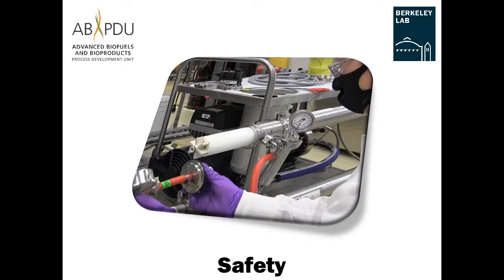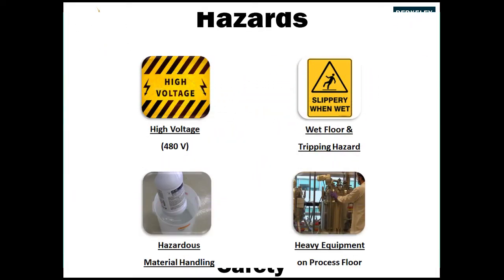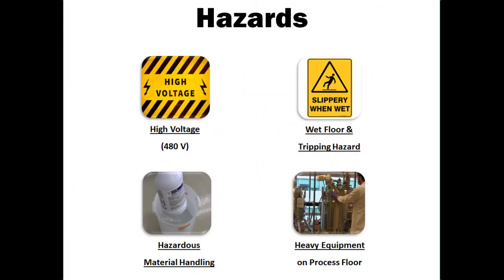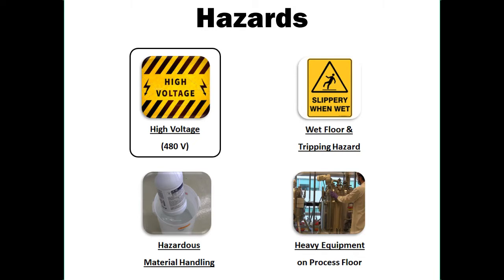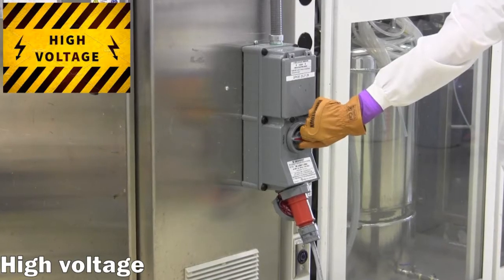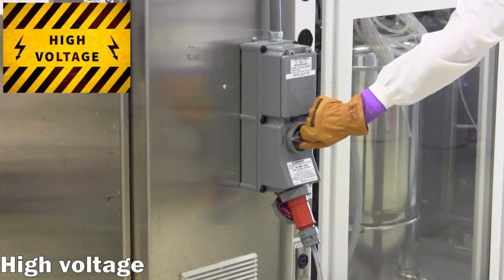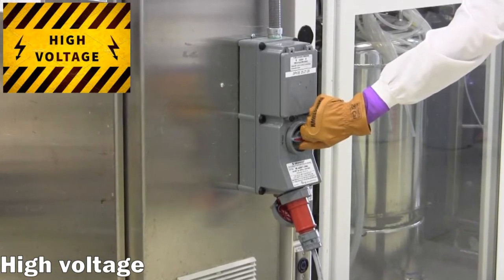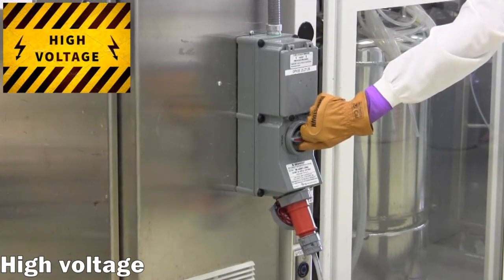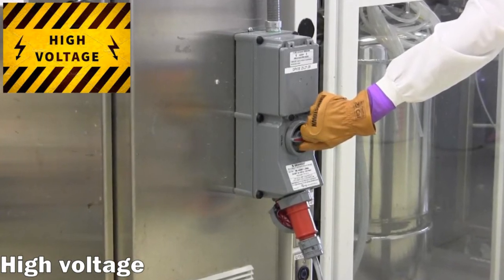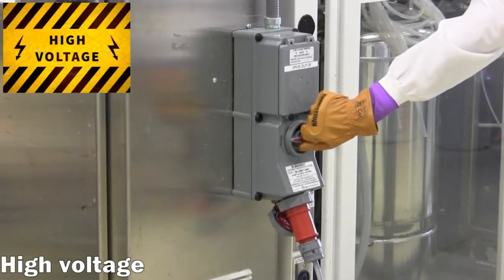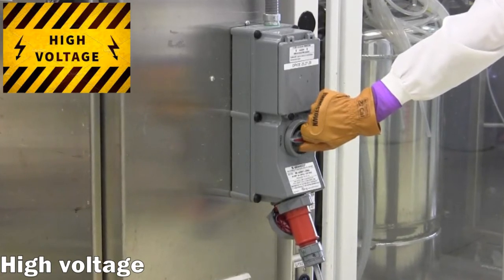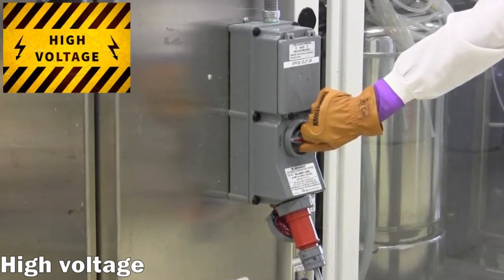Safety. There are a number of important hazards to be aware of while operating the M20 filtration system. The M20 requires a high voltage electrical power source in order to drive the pump. In the unlikely event of a malfunction, shock or arc flash from a 480 volt source can cause serious injury or death. Therefore, it is critical that researchers have completed the requisite electrical switching training and wear appropriate PPE while powering the equipment.